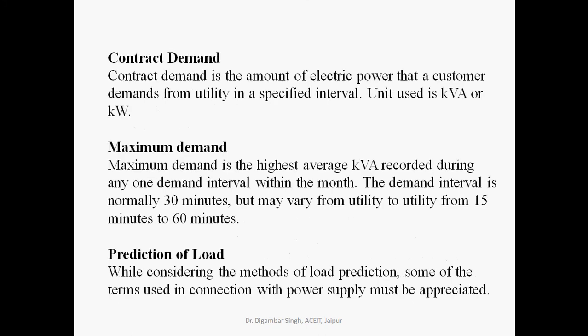The next topic is contract demand. Contract demand is the amount of electric power that a customer demands from the utility in a specified interval, measured in kVA or kilowatt. The maximum demand interval is 15 minutes at the national level, but at the local level it can be 30 minutes or between 15 to 60 minutes at different distribution centers. Maximum demand is the highest average kVA recorded during any one interval within the month.